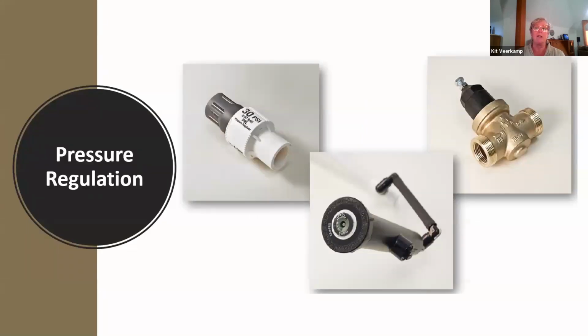Pressure regulators are very important because even within a city, even within a water provider district, everybody's not going to have the same pressure. So knowing what a pressure regulator is and using it if necessary is important. Oftentimes, pressures can vary from 10 PSI, pounds per square inch, to 100. And it's oftentimes necessary to deal with these.